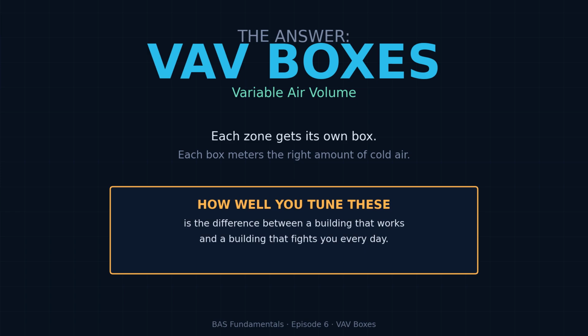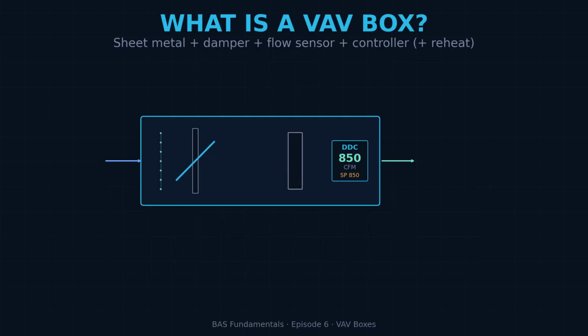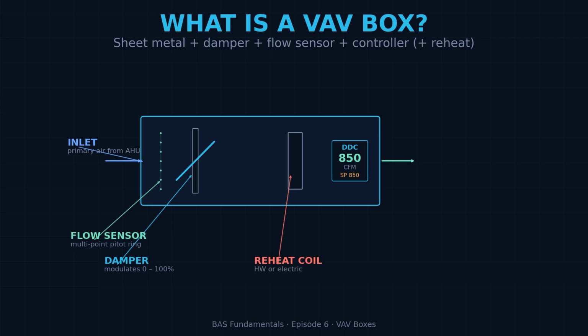That's the VAV box's job, and how well you tune it is the difference between a building that works and a building that fights you every day. So what is a VAV box? Physically, it's a sheet metal box sitting in line with the ductwork, usually above the ceiling. Inside, you've got an inlet, a damper blade, a flow sensor, a DDC controller, and on many boxes, a reheat coil, either hot water or electric. One box per zone or per zone group.